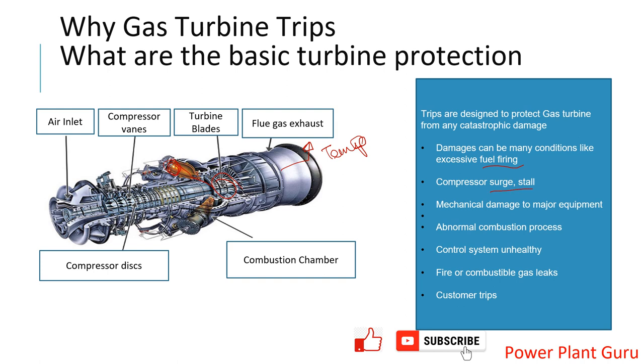The next category is compressor-related. Any compressor needs to be protected from surging and stalling phenomena. In a gas turbine this may also occur during startup and shutdown. Various types of compressor protections during startup and shutdown are given, like bleed valve position and IGV position. This type of trip is given for compressor surge and stall protection.